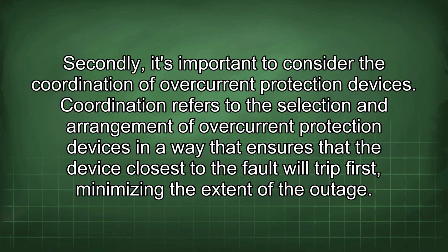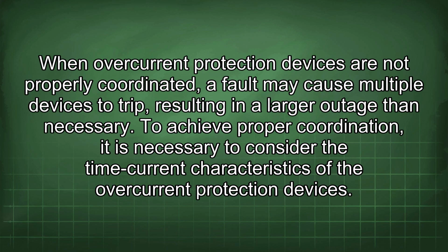Secondly, it's important to consider the coordination of overcurrent protection devices. Coordination refers to the selection and arrangement of overcurrent protection devices in a way that ensures that the device closest to the fault will trip first, minimizing the extent of the outage.